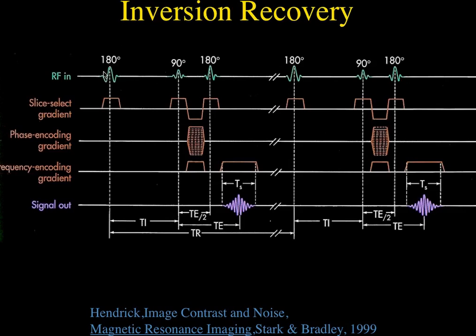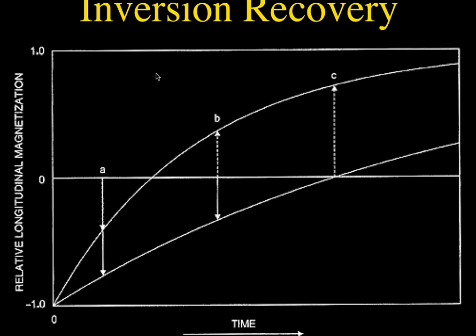You can also do this using first an inversion pulse — inversion recovery. You give a 180-degree pulse first, wait until the magnetization starts recovering, then give a 90-degree pulse, 180-degree pulse, and get an echo. If this TI time is fairly short, you can nullify fat signal; if it's longer, you can nullify water signal. That's how we get STIR images and FLAIR images. If TI is short, you catch fat when it has zero bulk magnetization in the z-direction — the 90-degree pulse produces nothing from fat.